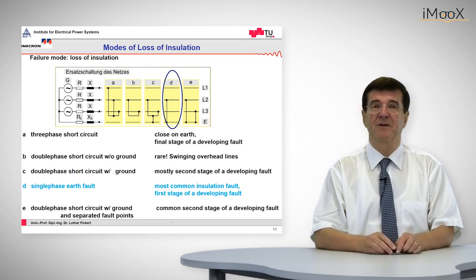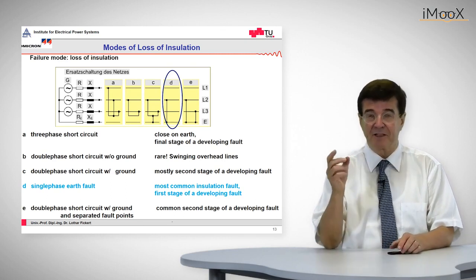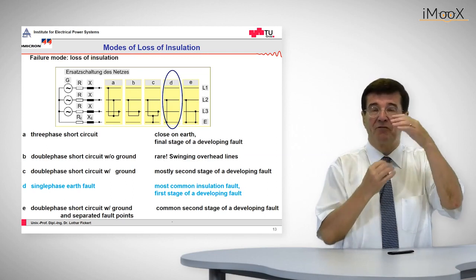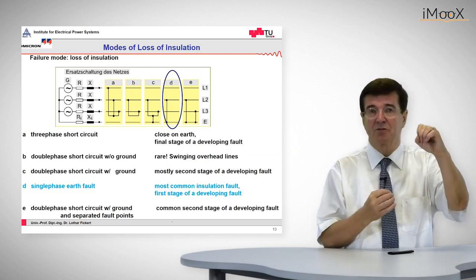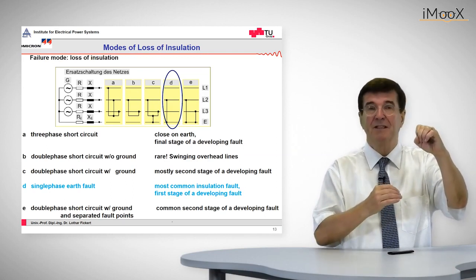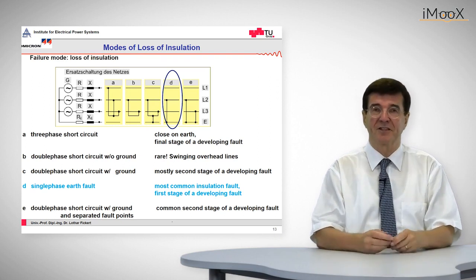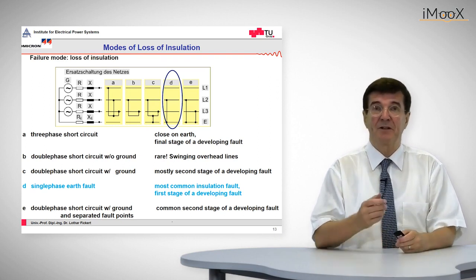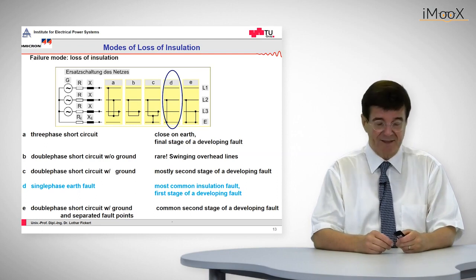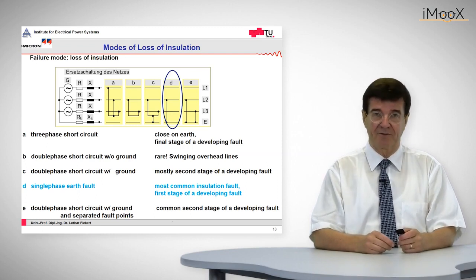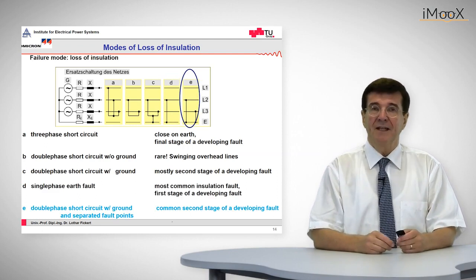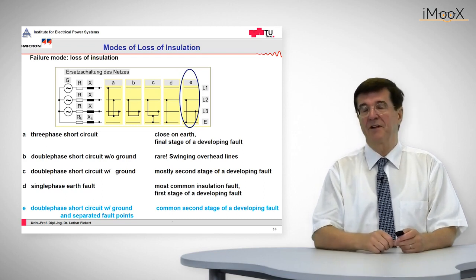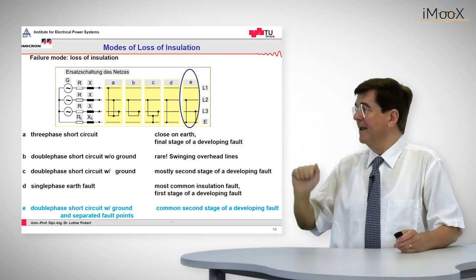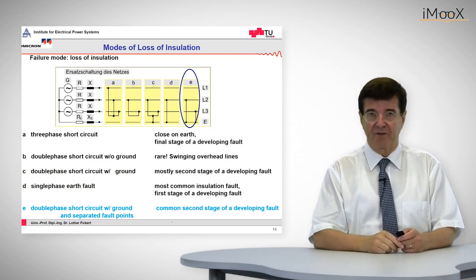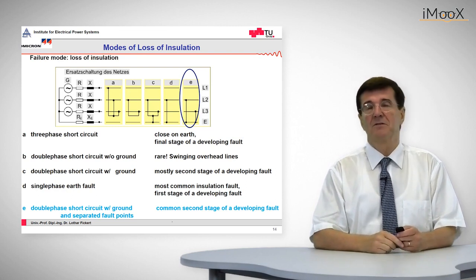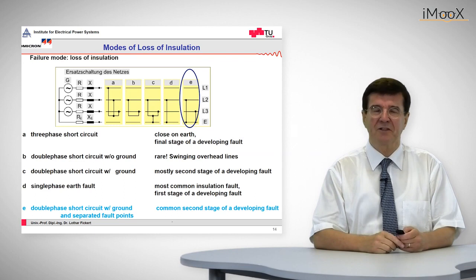this is caused by the breakdown of insulation. Breakdown of insulation means we have a field between the hot conductor and the cold ground. And if this insulation does not sustain this field anymore, then we have an insulation breakdown, and this is a fault between phase and ground. The last fault, which is classified here as E, is the so-called cross-country fault. This is a double ground fault in two different phases.